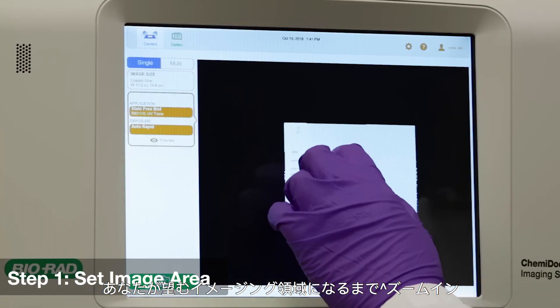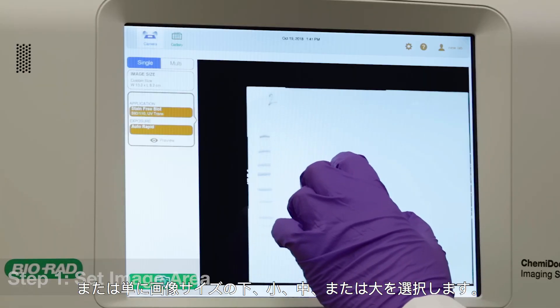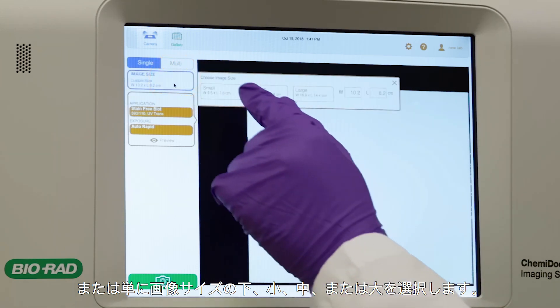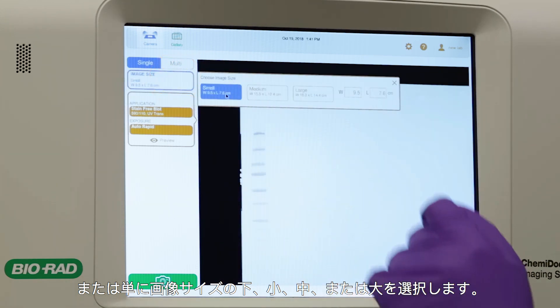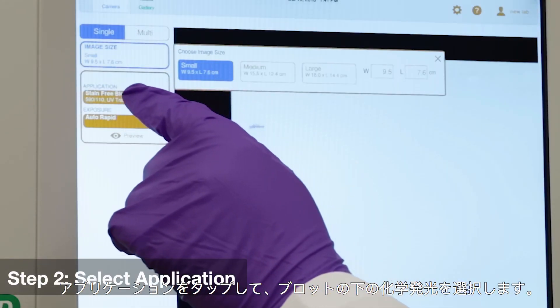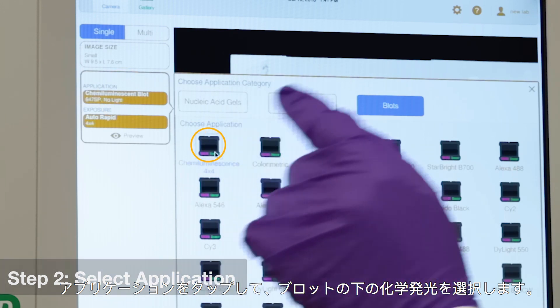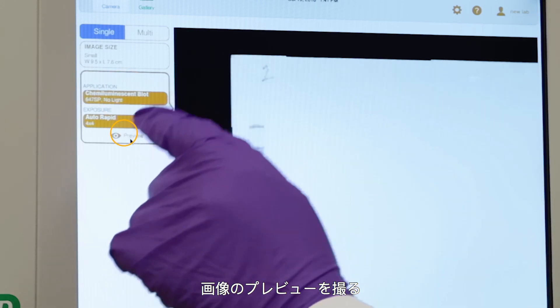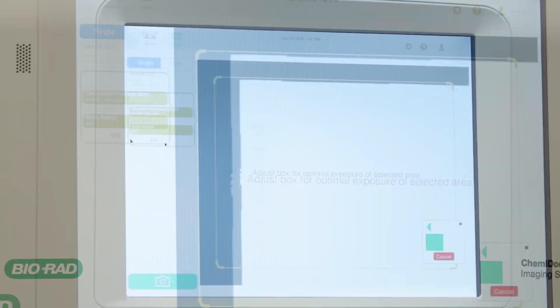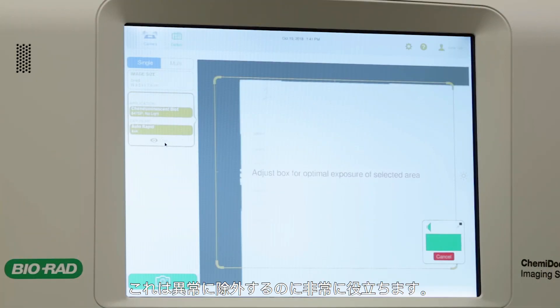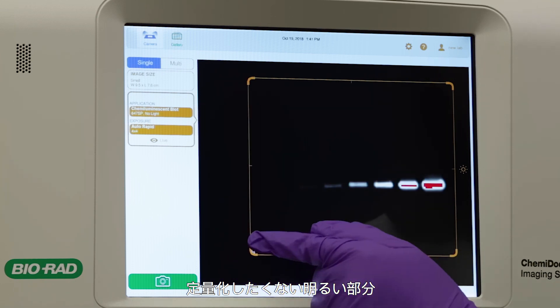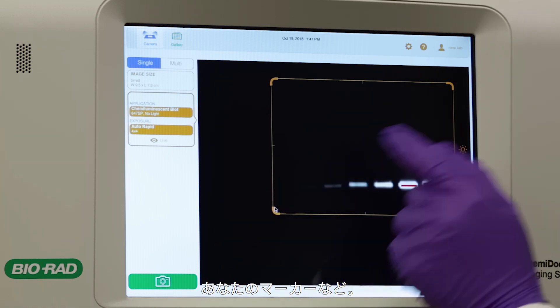Zoom in until you have the desired imaging area, or simply select small, medium, or large under image size. Tap application and select chemiluminescence under blots. Take a preview of your image and set your region of interest. This can be very useful for excluding abnormally bright areas that you won't want to quantify, such as your marker.